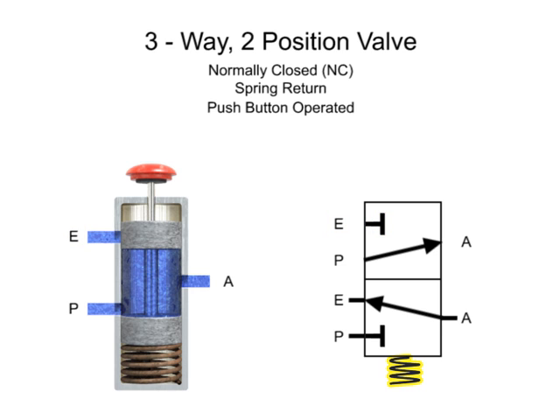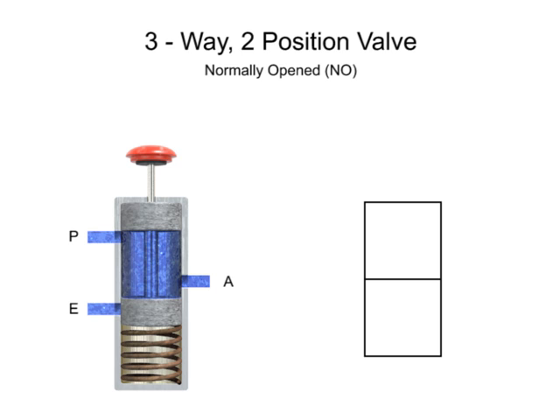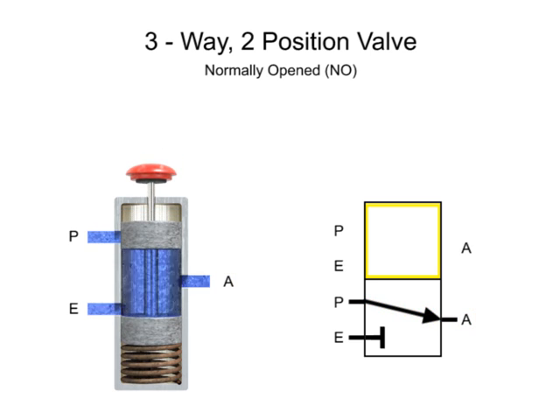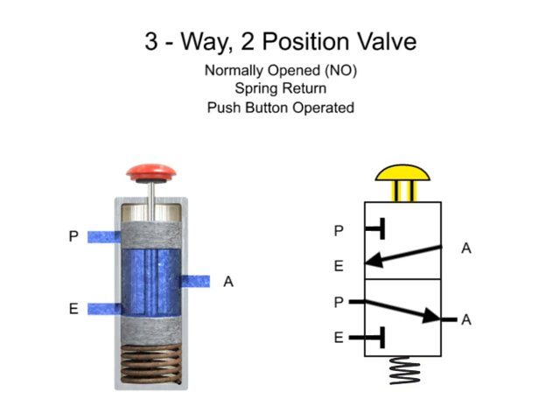The valve is also spring return and push button operated. Here is another three-way, two-position valve. This valve also has an inlet port P, exhaust port E, and output port A, but they are in a different configuration. In its normal position, exhaust port E is blocked and fluid flows from pressure port P to outlet port A. The second position pressure port P is blocked and allows fluid to flow from outlet port A to exhaust port E. The valve is also spring return and push button operated.